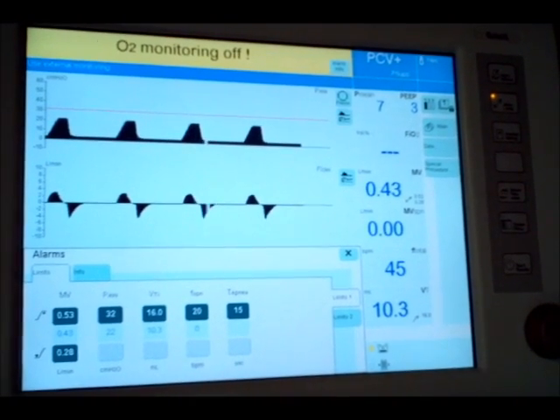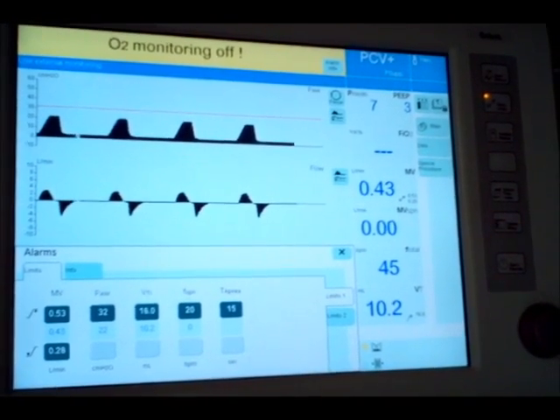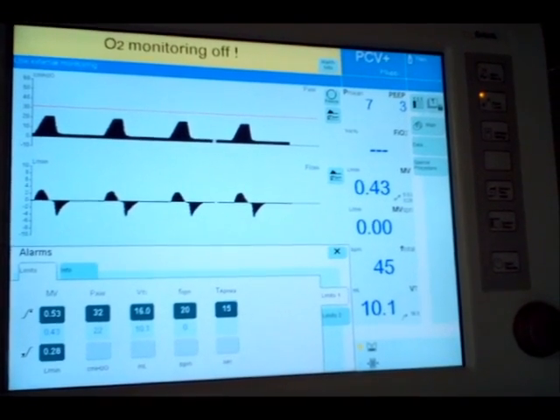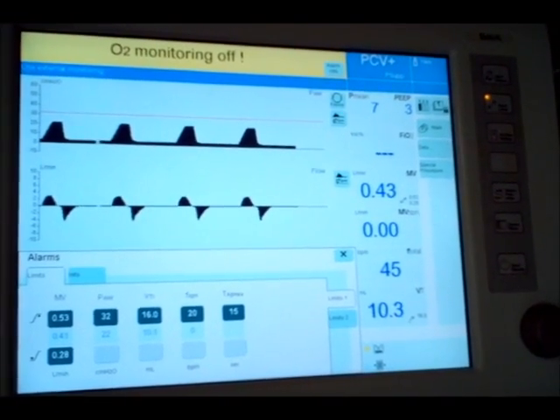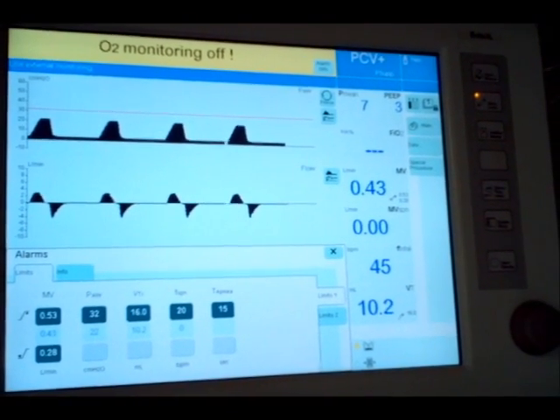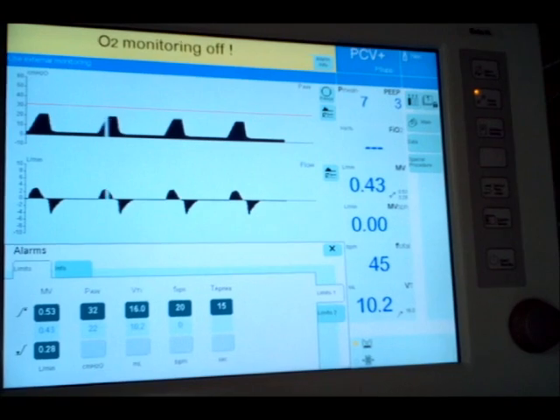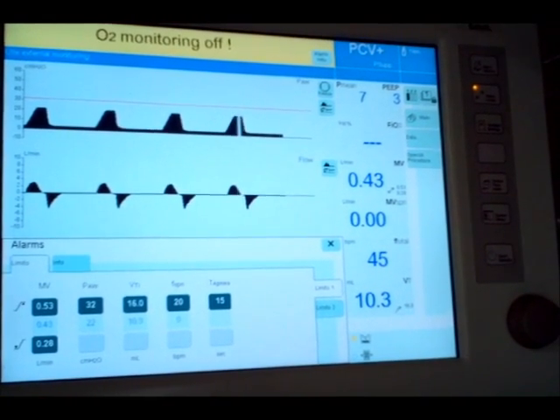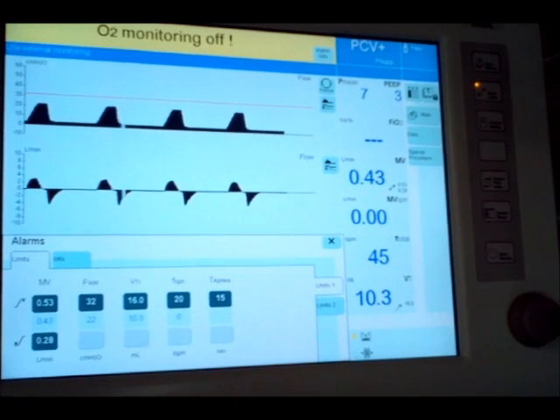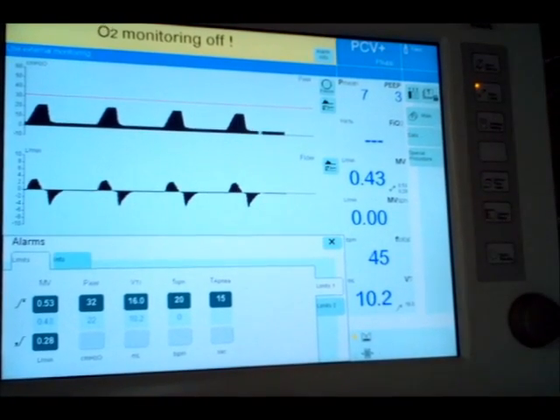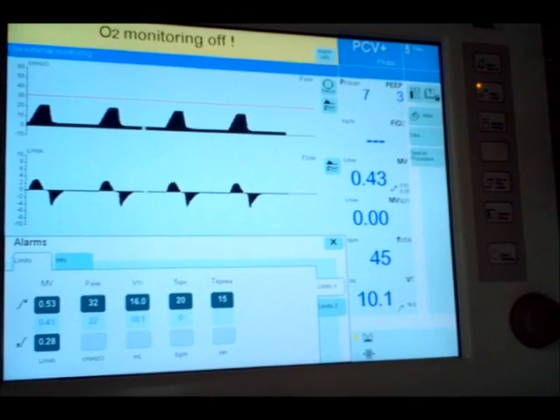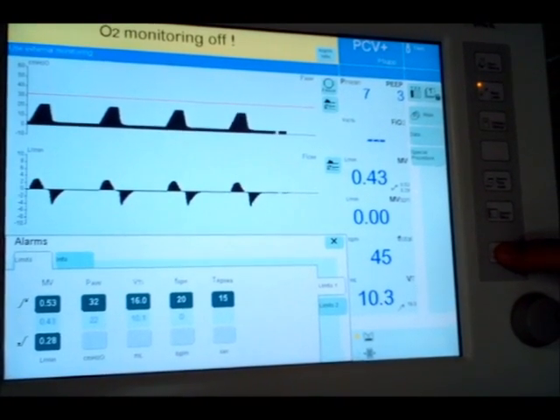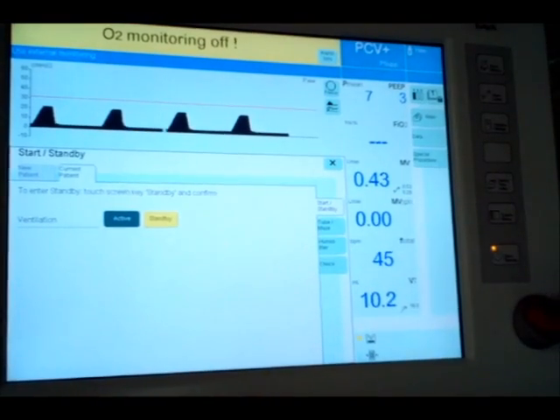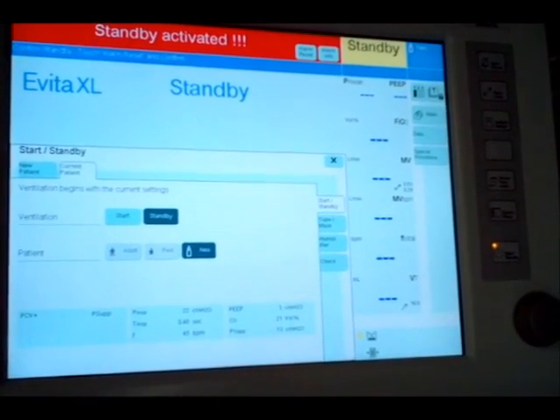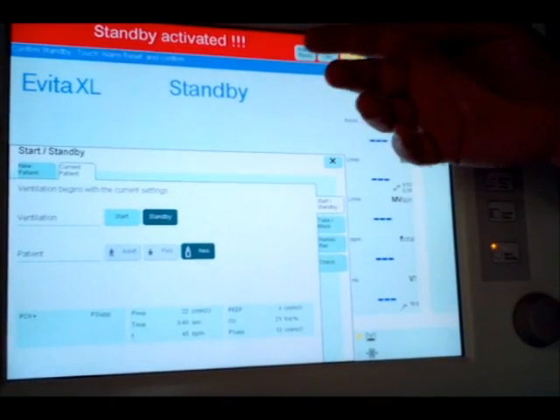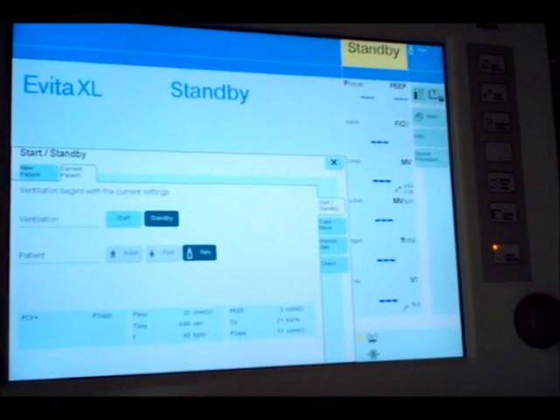And then the other thing you really need to know how to do is put the ventilator in standby, okay? So let's say we're going to take the baby to surgery, or we're going to take them on a transport somewhere. With the newer generation ventilators, if you power it down and power it back up, you've lost all your settings. So this allows us to keep our settings. The standby button is down here. Press standby, it's in yellow. It comes on with an alarm to make sure, are you sure you want to do this? Press your alarm reset, and then we're in standby.